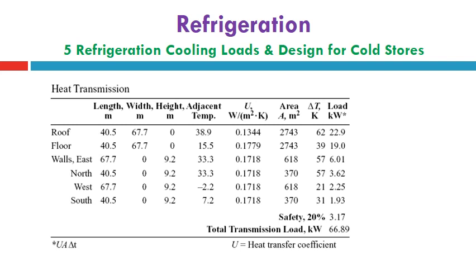66.89 kilowatt, by multiplying all the delta T by the area of each wall exposure according to its length, width and height, and its adjacent temperature to get the temperature difference, and finally using the U, by multiplying A by U by delta T, after getting the product of the area according to the length and width.